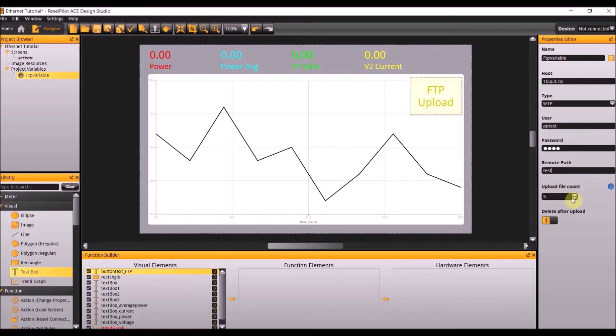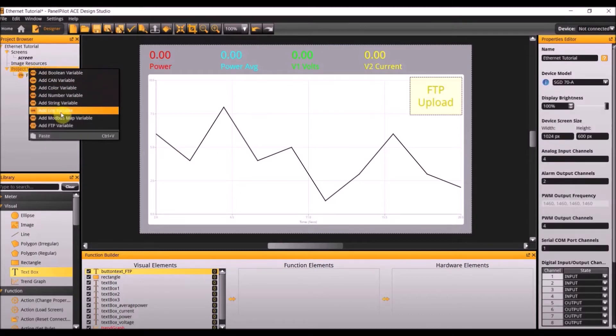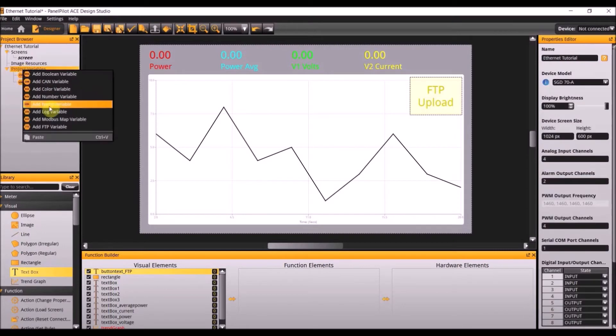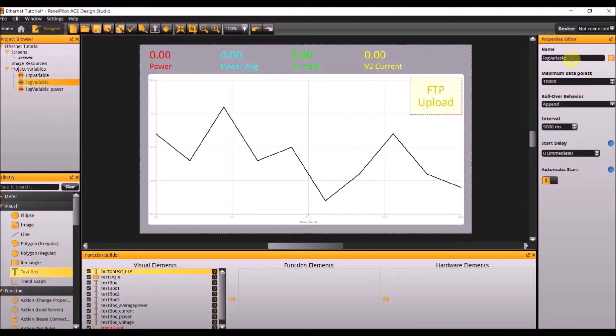The upload file count is 5. The second project variable we need is a log variable, so again right click on project variables and add log variable. Name it log variable power, with a maximum of 10,000 data points, append the rollover behavior, an interval of 5000 milliseconds, and a start delay of 0. Add another log variable and name this one log variable power average. Again the only thing we need to change is the interval to 3000 milliseconds. At this point the project variables are complete.